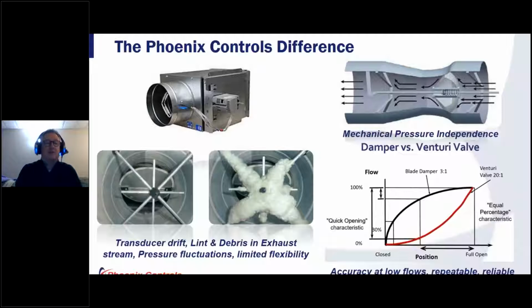So we all know what a VAV box is, right? It has a blade damper inside there. It has a transducer that measures the pressure in the ductwork. And by measuring that pressure in the ductwork, it finds its position in order to try to manage the airflow, right? And obviously managing airflow with temperature control as well. But over time in a hospital, especially on the exhaust side, that lint can build up on that transducer. Right, and this is the picture you see here in the bottom left corner. Right after around 6 to 9 months in a hospital, that lint can build up on that exhaust valve and cause a drift of around 25 to 30%. And that also, with that pressure drift and also with the constant positioning and measuring, we see pressure fluctuations. Right? And pressure fluctuations at the end of the day can result in compromising the directional pressure, especially, like I said, for some of these more critical spaces like isolation rooms and so on.